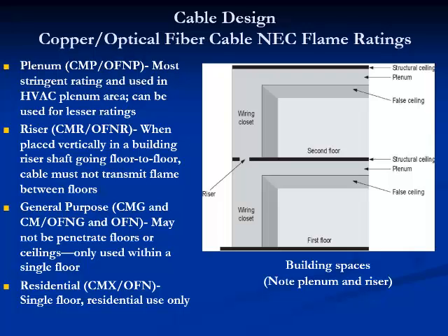Riser, or CMR for copper, and OFNR for fiber. When placed vertically in a building, in a riser shaft going floor to floor, cable must not transmit flame between floors. General purpose may not be used to penetrate floors or ceilings, only within a single floor. Residential is simply for single floor residential use only, and fiber and coax jackets follow the same rating as copper but use different markings on their jackets.